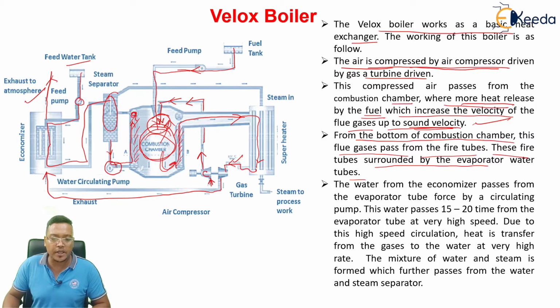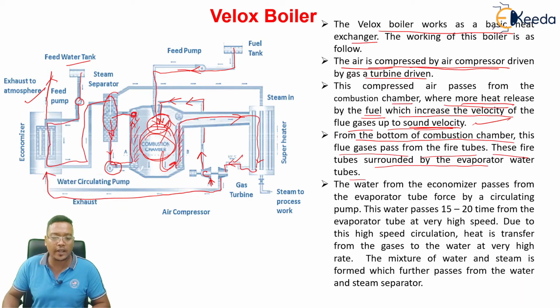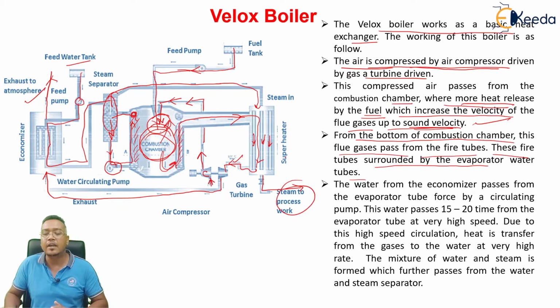The steam and water mixture will go into the steam separator. Water and steam will separate. The water will go like this and the steam will go into the superheater tube. And after the superheating of the steam, this superheated steam will enter the steam turbine for further processing. This is the steam and water cycle. So friends, I have covered the steam and water cycle and the flue gas path in the Velox boiler.